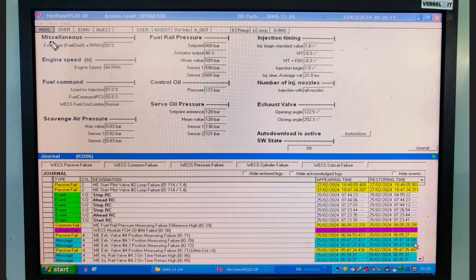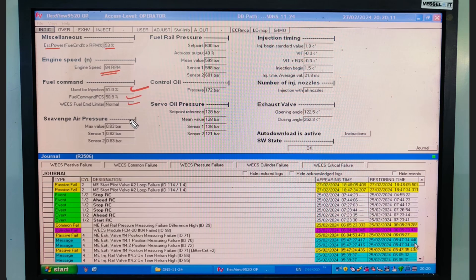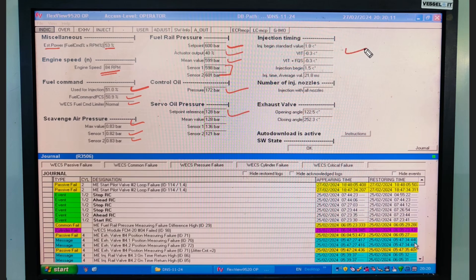In the Indication tab you can see the estimated power, fuel command versus RPM - this is the percentage of fuel command versus RPM. You can see the engine RPM and fuel command. Parameters shown include scavenge pressure with two sensors, fuel oil rail pressure with both sensors displayed.